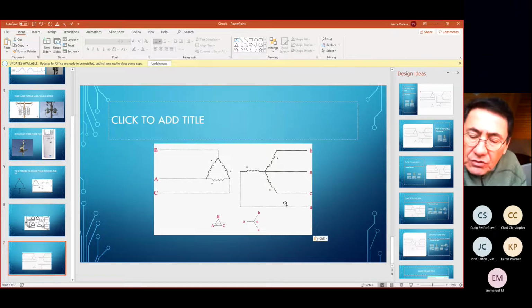The amount of money to install the Strikesorb, typically $700 to $1,000 added cost to the installation, is insignificant compared to the cost of blowing up the drive. Why do we have these voltage variances, and why do we need this extra $700 to $1,000 expenditure? Lightning striking beyond a certain distance from your VFD need not blow it up, but it will cause significant voltage surges on the power line. If you have a Strikesorb, you will be able to survive those. It's very hard to survive a direct lightning strike, and there's really not much that we would put in place for that. But lightning strikes in the area, which are very common in the Central Valley, are going to cause voltage surges that will cause damage if you don't have the Strikesorb. So that's one reason.